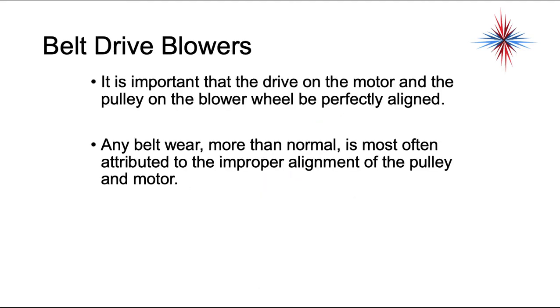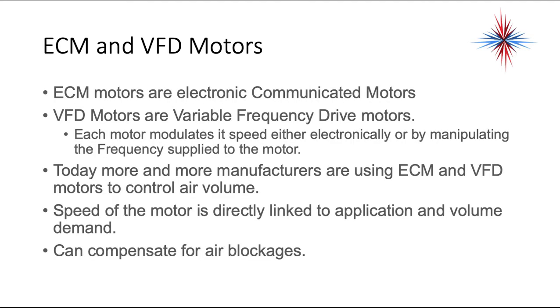It's important that on belt drive blowers, the drive and the motor on the pulley are perfectly aligned. You can't have any offset because the belt will start wearing. Any belt wear more than normal is often attributed to improper alignment of the pulley and motor. You don't want to have to go out and replace belts on negative 10-degree days on a roof.